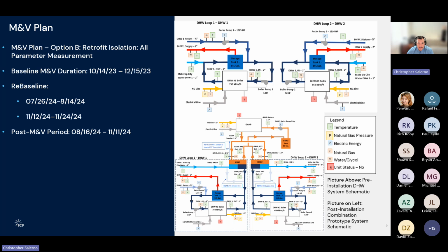So essentially, this gas-fired heat pump operates on a closed water glycol loop, as you can see up here in the orange, and goes to and from two separate individual plate and frame heat exchangers, going to each system. The cold water will come in, heat up to a certain point, and then go back to the system. Ideally, the boilers would not have to turn on if this system is running efficiently and optimally. That's ideally what the initial design of the system was. It didn't incorporate the preheating recirculation load, for simplicity. Based on our initial measurements, it was assumed that this system should have provided enough load for these, but we'll get into why it actually did not later.